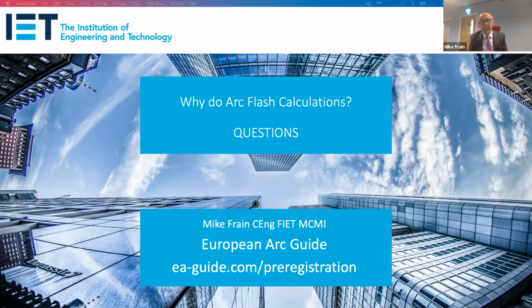But don't forget, there are going to be many cases where you can't reduce the incident energy level no matter what you do. You can't reduce it below 1.2 calories per square centimetre, as I suggested earlier. But you could probably do it for 90% of the cases—I'm sticking my neck out on that, but that's my experience. You can actually reduce it below those levels by good engineering practices.